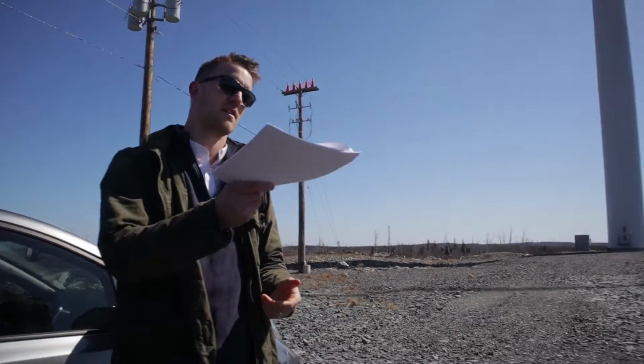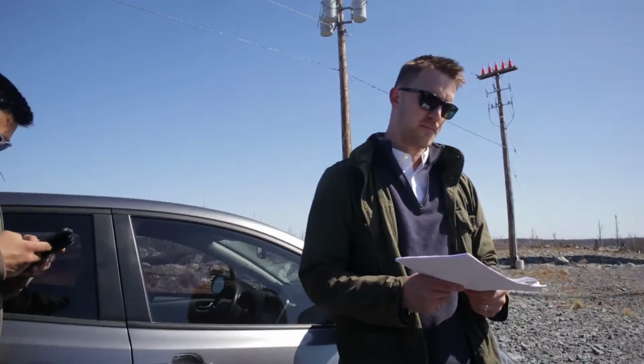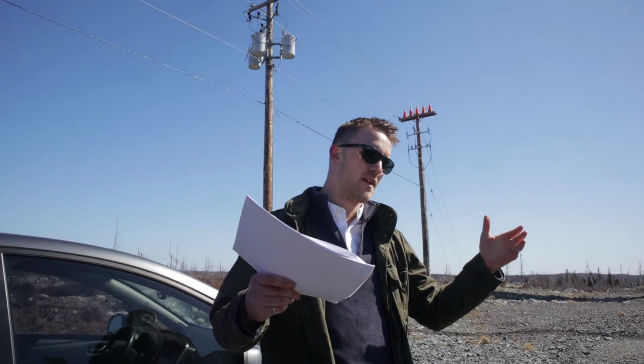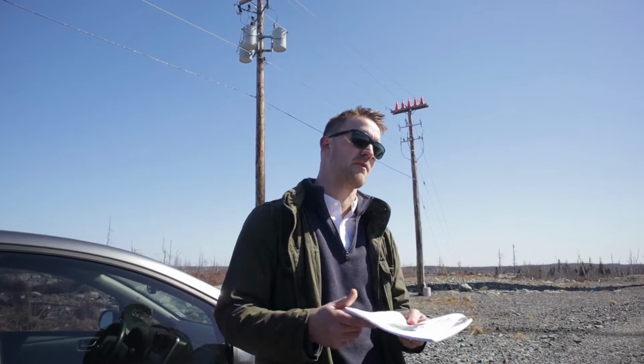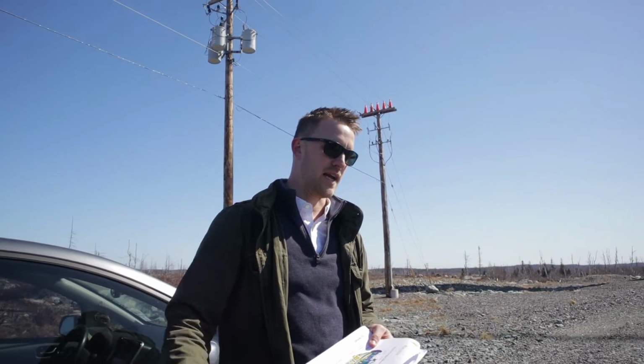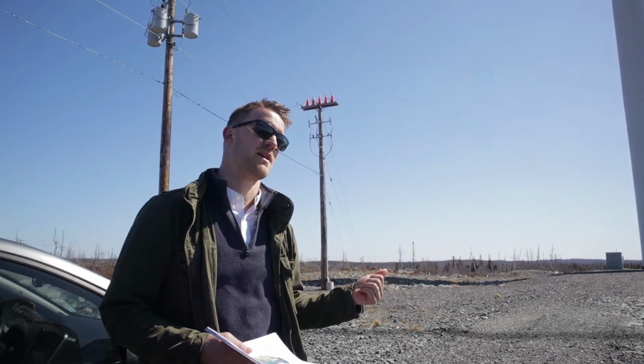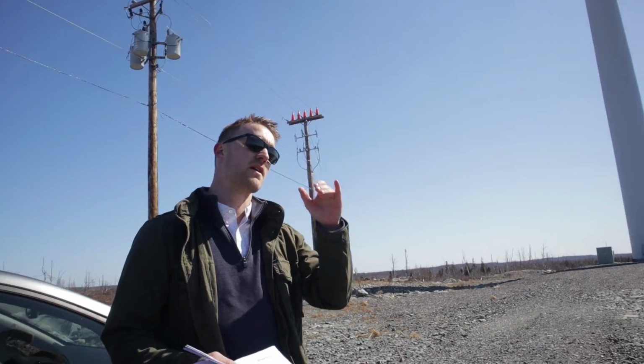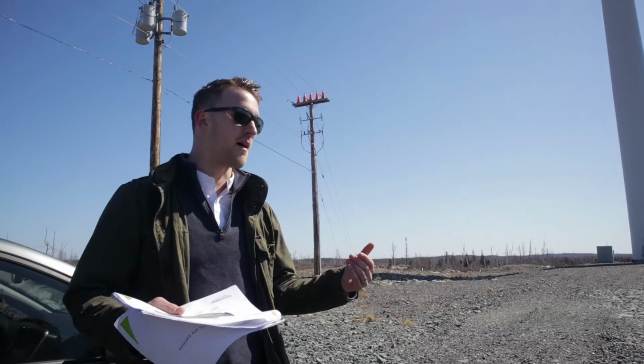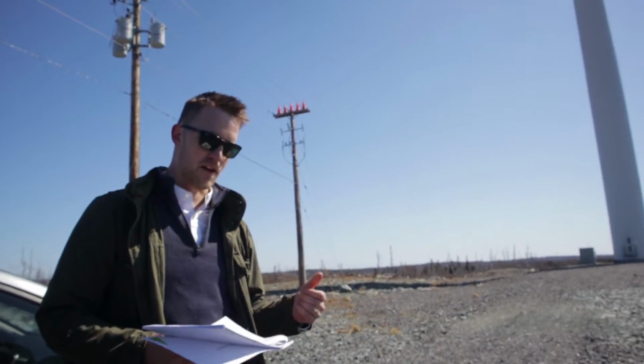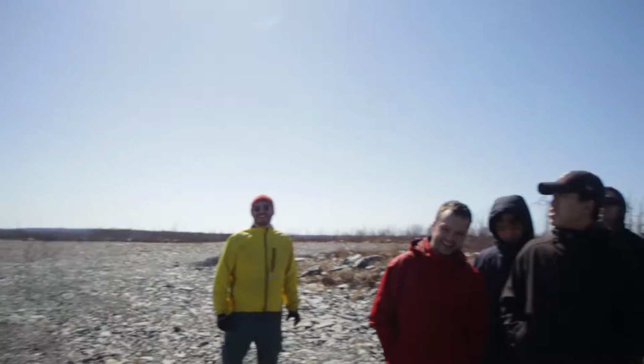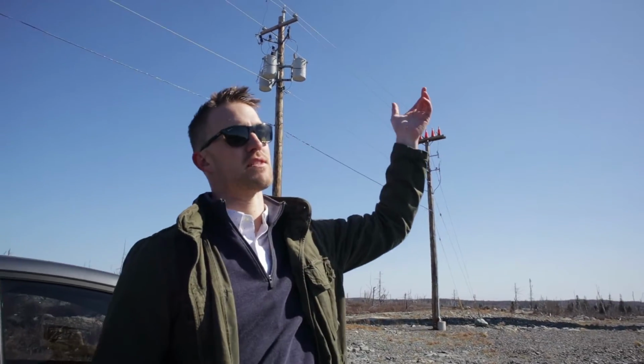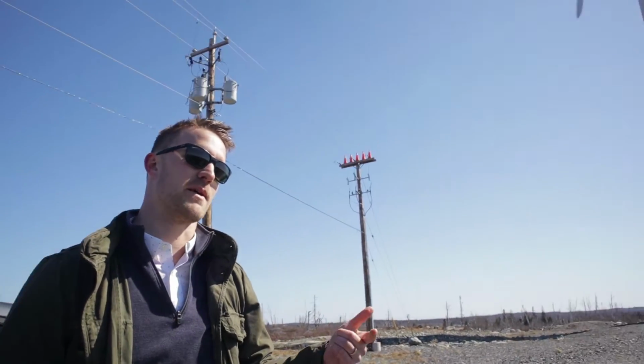You said doubly fed. What does that mean? Most traditional generators would have a single source, where the stator might be outputting or taking power, like a motor or a generator. We're doubly fed in that we've got active power on both our rotor and our stator. There's a big slip ring on the back of the generator, with a lot of power going through it, feeding the rotor. What that does is give us variable speed, because we need 60 hertz coming off that stator at all times, since we're feeding that straight to the grid. To be perfectly honest, as a mechanical guy, it's a lot of black magic to me, but the converter does some really cool black magic and lets you run the machine at variable speed. So right now we're pushing 60 hertz to the grid, even though that generator is not turning at 60 hertz. If that makes sense.